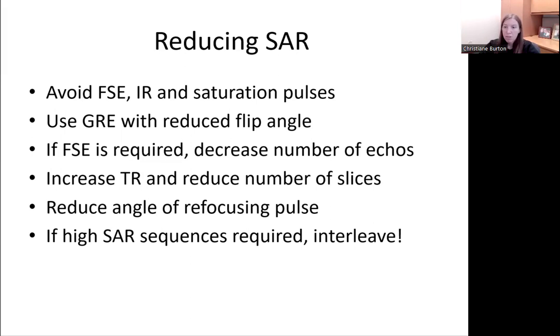As a rule, gradient echo sequences produce much lower SAR effects as they use gradient reversals rather than refocusing pulses to rephase the MR signal. Exceptions to this rule are GRE sequences performed at extremely short TRs, such as bSSFP, FIESTA, and TOF MRA, the latter of which also include traveling saturation bands that add to the SAR load. If these sequences must be used, interleave them in the protocol with lower SAR sequences to allow tissue cooling in between. You also need to understand that by reducing SAR, there are consequences, as I will explain in the next slide.